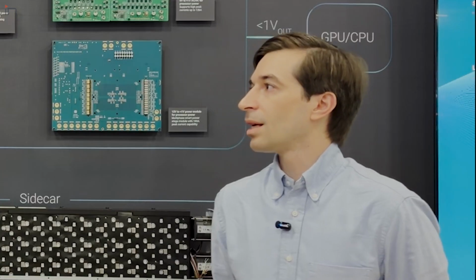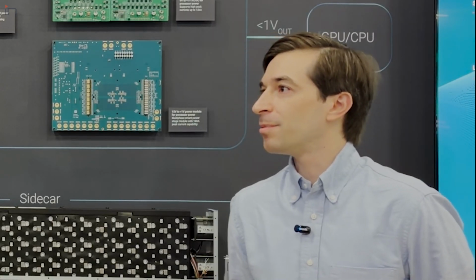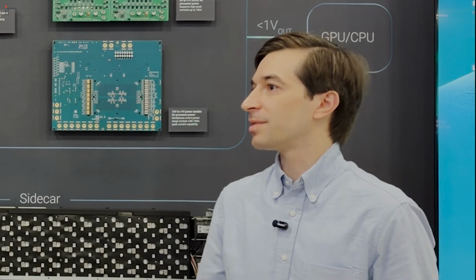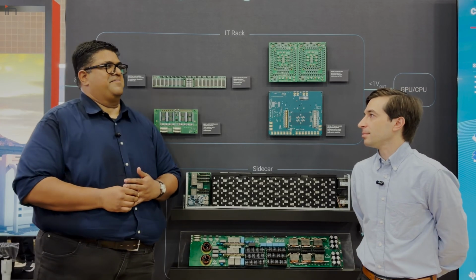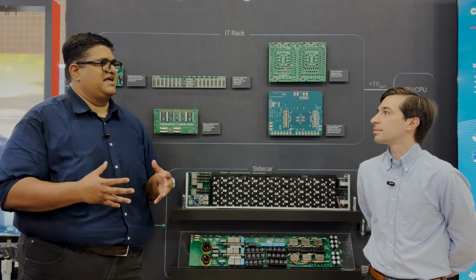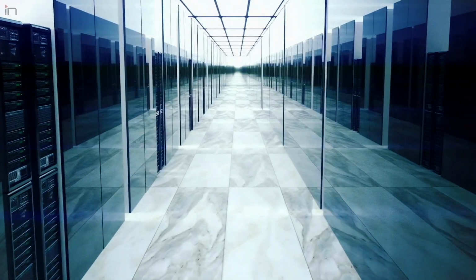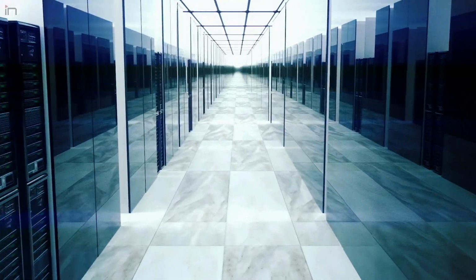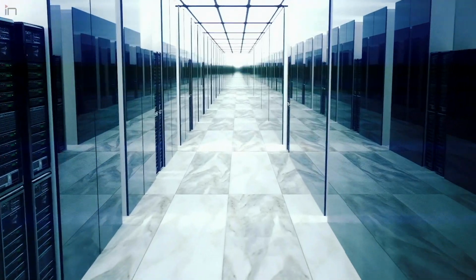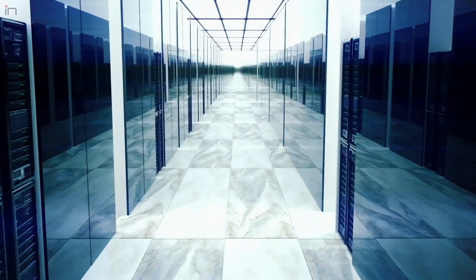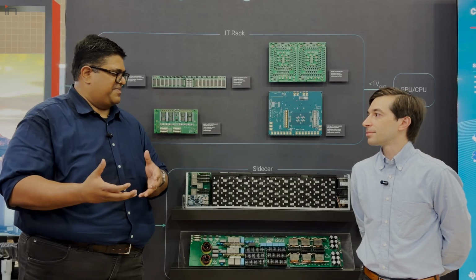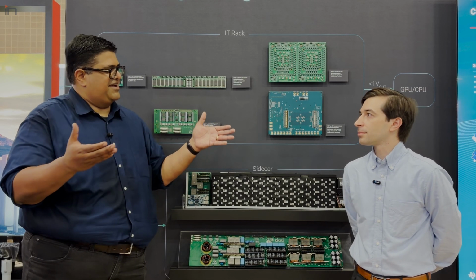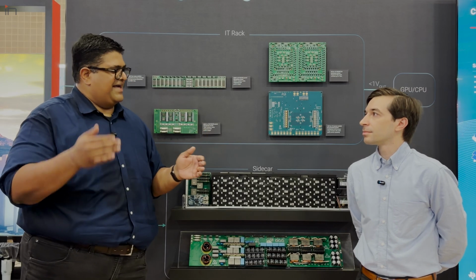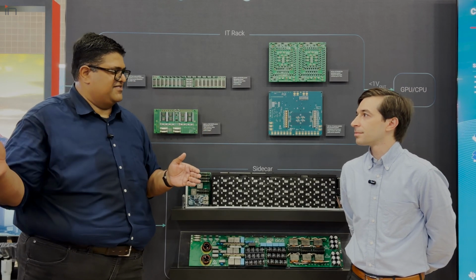So you mentioned that in the future, the 800 volts is going to get very close to the processor—where is it today? Today, 800 volts isn't even necessarily in the data center in that capacity right now. Today what you have is regular AC power coming in through the walls, and we basically have power supplies that go from AC to DC down to say a 48 to 54 volt backplane, and that is what gets fed into the servers.